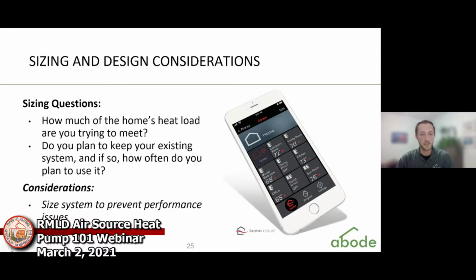If you keep your existing heating system running in tandem with an air source heat pump, it's important to consider how the existing heating zone will interact with the area the heat pump will condition. There are a number of good strategies to address this, including integrated controls, as Sean was mentioning. Integrated controls are thermostat systems that can talk to your heat pump and your existing heating system. If integrated controls won't work for your specific scenario, there are other ways to stage the existing system and the heat pump so they work together instead of compete with each other. Next slide.